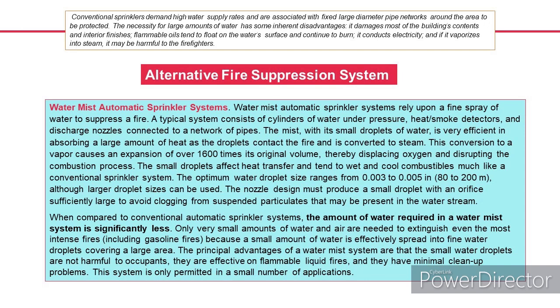When compared to conventional automatic sprinkler systems, the amount of water required in a water mist system is significantly less. Only very small amounts of water and air are needed to extinguish even the most intense fires, including gasoline fires, because a small amount of water is effectively spread into fine water droplets covering a large area. The principal advantages of a water mist system are that the small water droplets are not harmful to occupants, they are effective on flammable liquid fires, and they have minimal cleanup problems. This system is only permitted in a small number of applications.